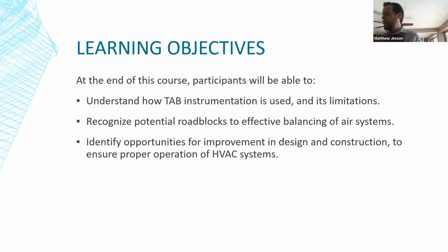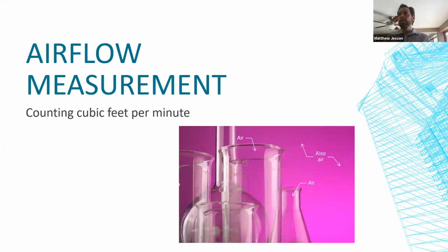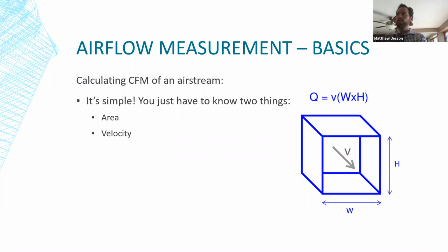So we'll get right into the first part here. Airflow measurement. How do we count up the cubic feet per minute that your system is delivering to a space? In principle, airflow measurement is very straightforward. If you have air moving through a duct, you just need to know the area and the velocity of the air. You multiply those two, and you've got your CFM. It's that easy. But as you can imagine, I couldn't really fill a full hour presentation just with that. So here are the things that can complicate that.